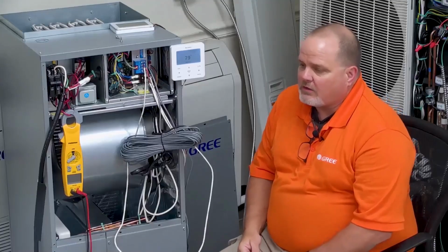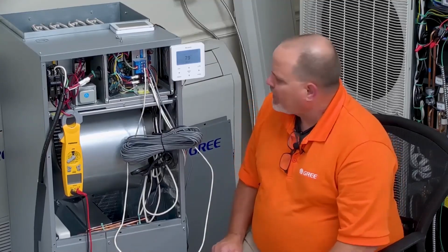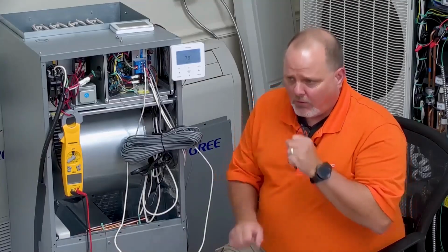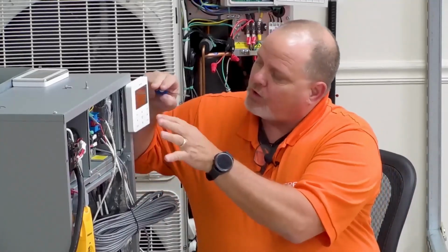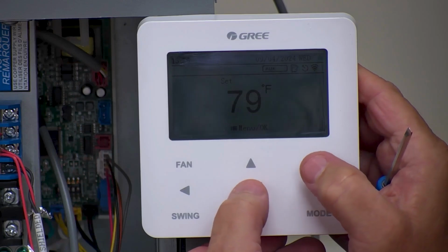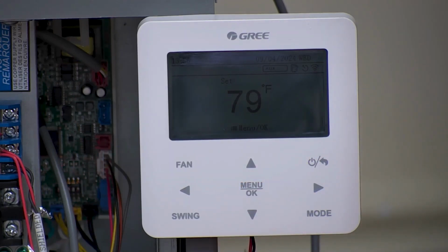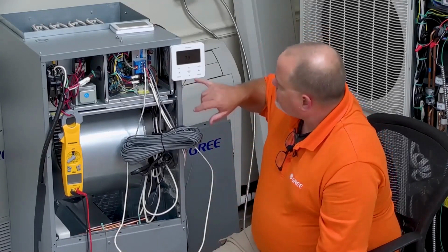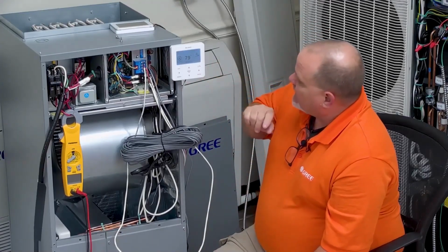Now, the controller doesn't come set up for eHeat function, and they should have it in the installation instructions. So if you have electric heat available, again, only on an air handler, when you first power it up, before you even turn it on, you hold the menu and power for at least 5 seconds, and it'll say setting is done. That means you now have the eHeat function, or eHeat mode, I should say. It doesn't come out of the box with eHeat mode. You have to enable eHeat mode. So now let me turn it on. So you can see I got eHeat mode.